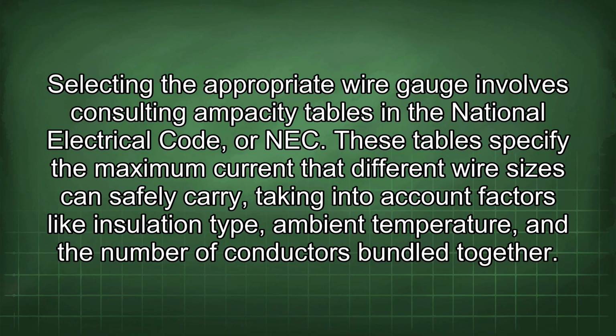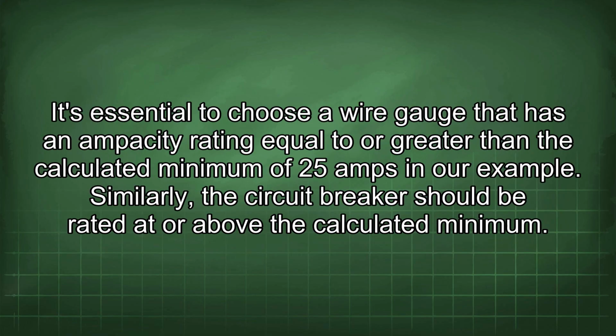Selecting the appropriate wire gauge involves consulting ampacity tables in the National Electrical Code, or NEC. These tables specify the maximum current that different wire sizes can safely carry, taking into account factors like insulation type, ambient temperature, and the number of conductors bundled together. It's essential to choose a wire gauge that has an ampacity rating equal to or greater than the calculated minimum of 25 amps in our example.